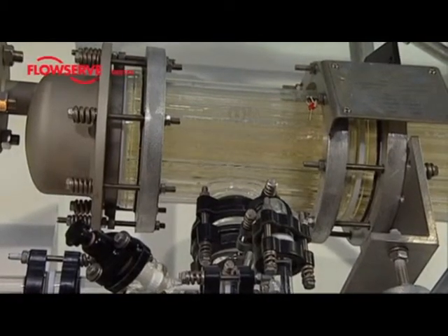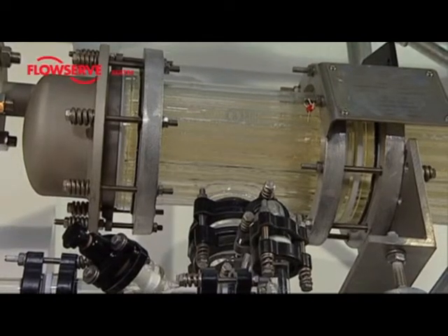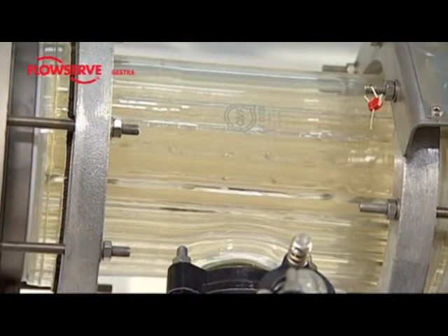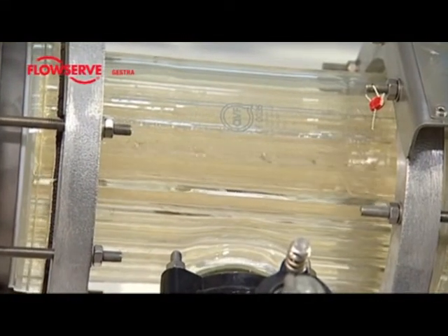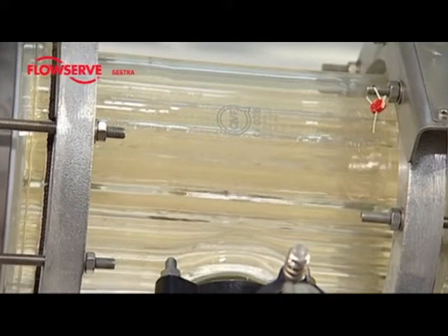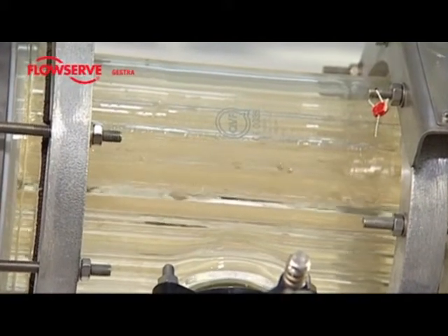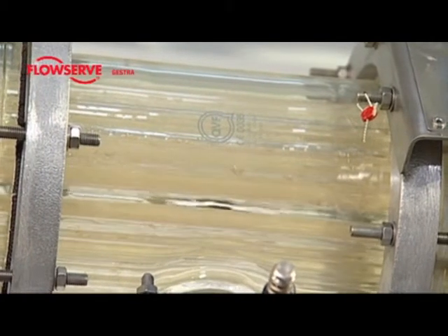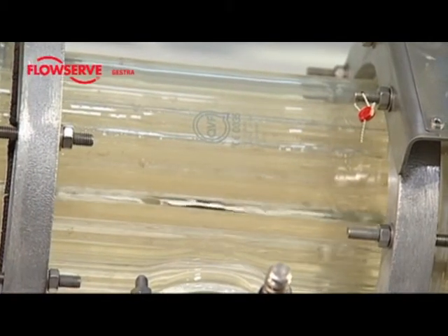This causes a banking up of condensate, which extends right into the heat exchanger and leads to the dangerous water hammer effect. An accumulation of condensate floods the heating surface, and the heat transfer coefficient is reduced by a factor of about 4. As a result, it's no longer possible to guarantee that the product passing through the heat exchanger is adequately heated at all times.